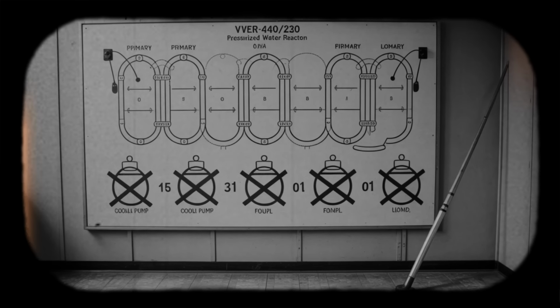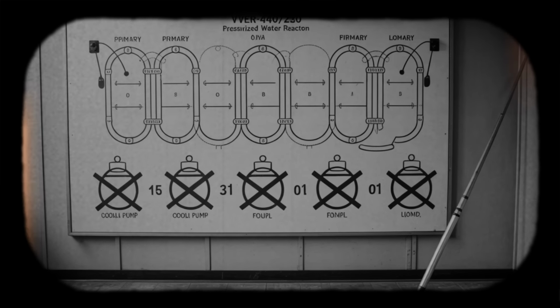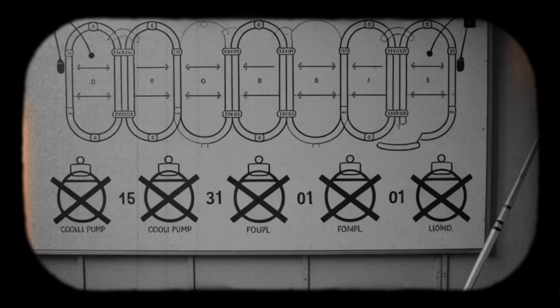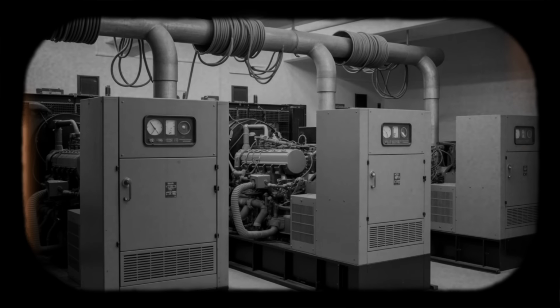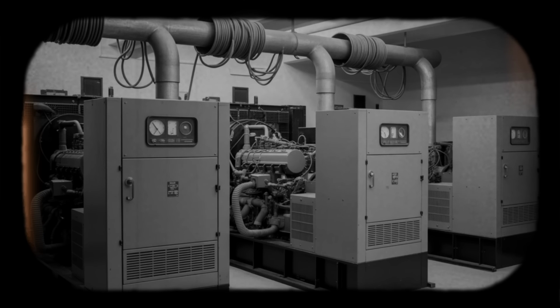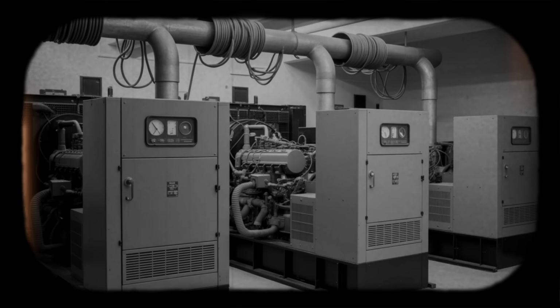While operators in the control room fought to maintain core cooling, the fire brigade fought to control the flames. The contrast between expectations and reality extended to fire protection itself. Design expectations: manual firefighting, supported by limited fixed water systems, is sufficient because fires are assumed to be localized and quickly detected. Plant fire brigades have adequate personnel and equipment for the fire loads present in nuclear facilities. Reality at Greifswald: the long turbine building, limited detection capabilities, absence of automatic suppression in most areas, and constrained smoke removal systems allowed fire and smoke to spread far along cable routes before crews achieved full control.